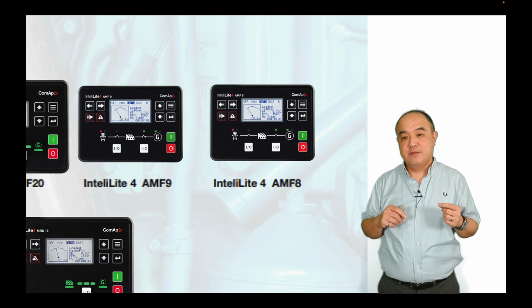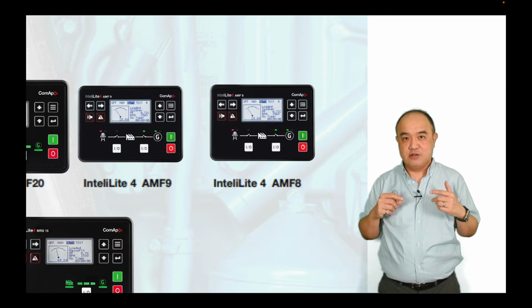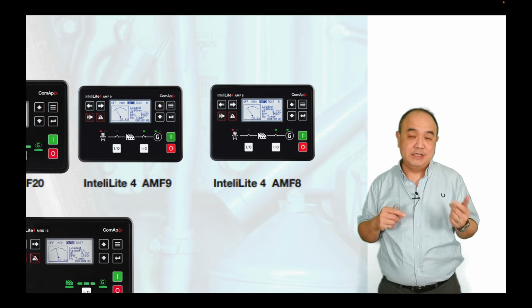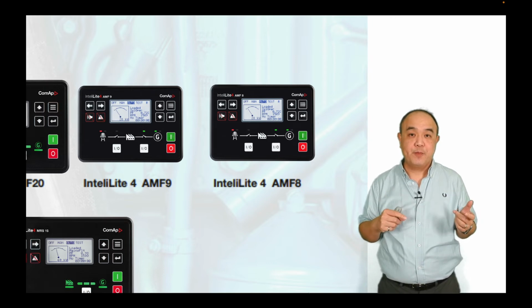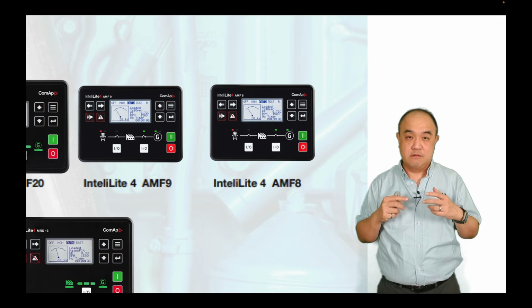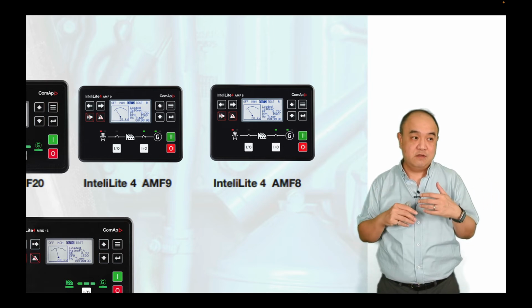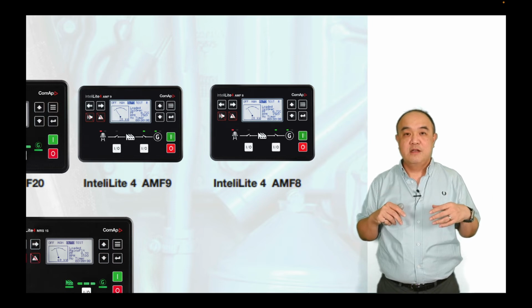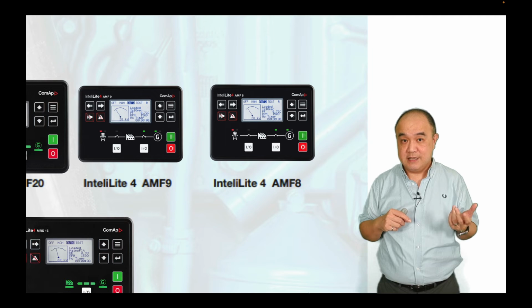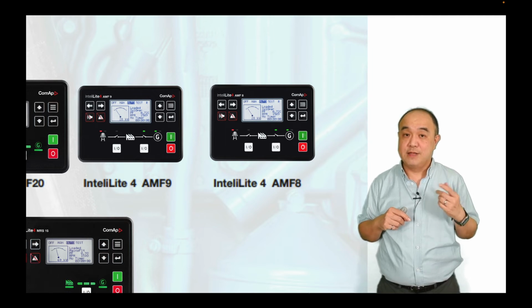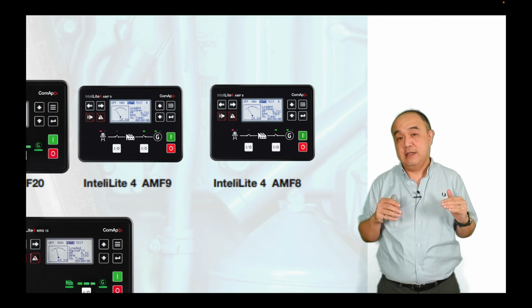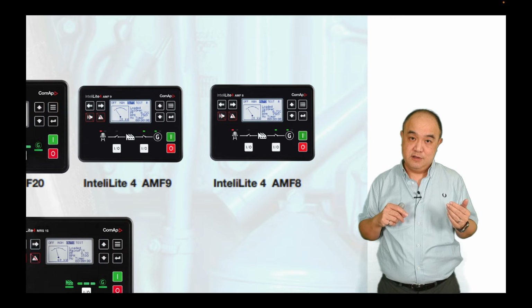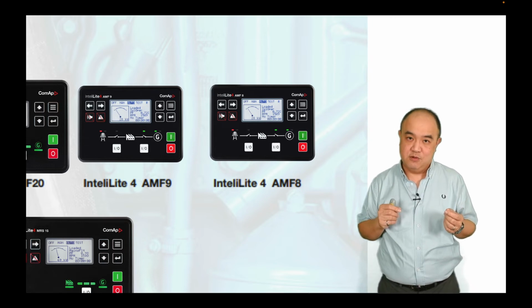The AMF9, so these two controllers both have a smaller cutout. And the AMF9 functionally has all the functions of the old ComAp AMF25 NT, which ComAp will be phasing out this year. So if you have older systems using ILNT AMF25, and you're looking for a one-to-one upgrade where you don't want different cutouts, and you don't want any software not supported, or any features not supported, the product to use to replace that would be the IntelliLite 4 AMF9. The only thing to watch out for is that all IntelliLite 4 series now have positive output. For more detail on that, I have links below to the IntelliLite 4 series. Let's take a look at the next slide.